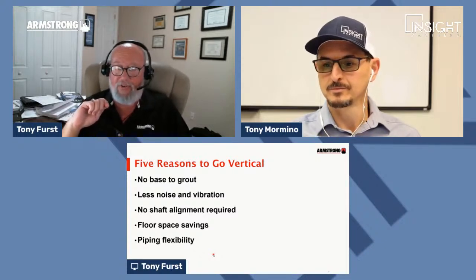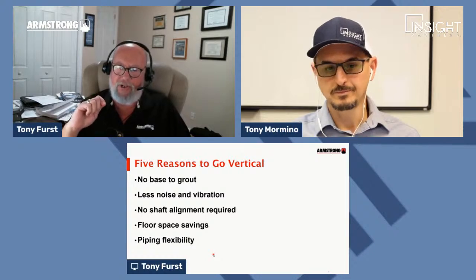Great question. It depends entirely on the size of the pump, but you've got to give the structural engineer the pump weight and how it's going to be hung. Most often it doesn't change the hanger requirements at all. If you look at the building code and mechanical code, both the IBC and IMC, and look at the hanger requirements, most of the time the hangers are way stronger and heavier than they need to be. What I've seen a lot is using isolation hangers or spring hangers on either side of the pump, right ahead of the 90s making the drops down to the pump, and a lot of times those get changed to spring cans to handle the spring load and any movement that may happen. Spring cans work a bit better, but that's an easy change. They don't really change the hanger loads much, but we can provide all the loading data, both dry and wet weights for the pumps, to help with that.